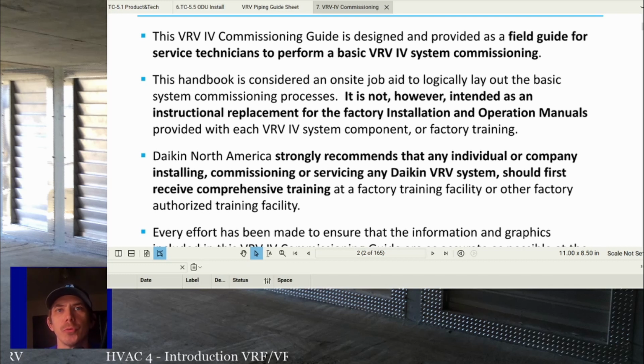So you need to make sure you're doing everything properly. What I like to say is you want factory quality work every single time. That means you purge while you braze, you follow good piping practices, you close up the system when you're done at the end of the day, you terminate your wires properly, you make sure that you don't have any connections that you can't get to later. All those little things, do it all to the best of your ability, because the last thing you want to have is a large system with copper shavings in it, or a bunch of oxidation from brazing in it, and it causing problems on multiple units, and you having to foot the bill of making all the necessary repairs to the system.